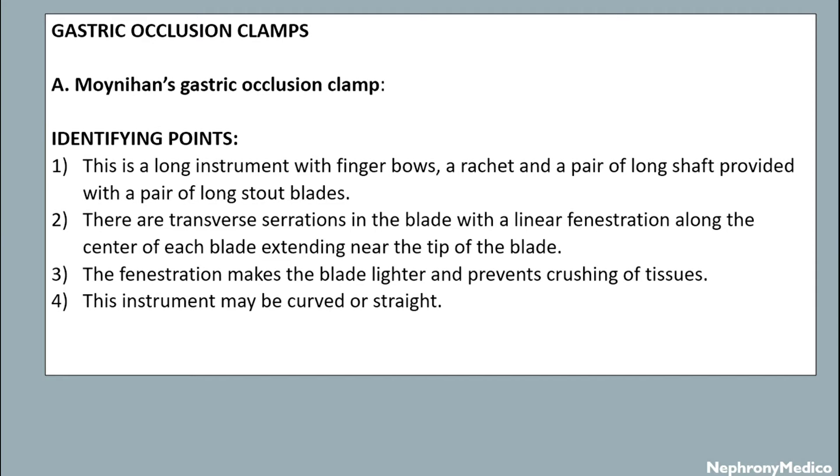Moynihan's clamp is provided with a pair of long stout blades. There are serrations in the blade with a linear fenestration along the center of each blade extending near the tip of the blade. The fenestration makes the blade lighter and prevents crushing of tissues.